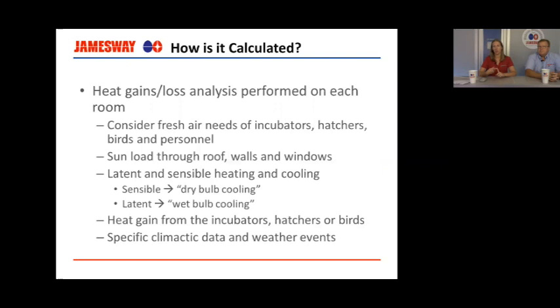And the one main mistake that I see a lot is that local contractors think that the people in the room need oxygen, need fresh air, but don't realize that the incubators and hatchers also need fresh air, which is crucial. In comparison, for one person, you want somewhere between 20 and 40 CFM of fresh air. For one P120 incubator, we need 500 CFM of fresh air. So there's a huge difference there, and that can be one area where problems arise.